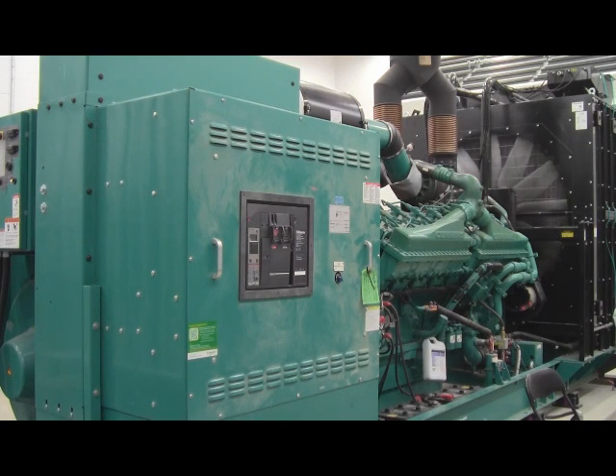This is the backup generator. It's all run to the PLC panel to kick in when the power goes out to the building and there's no power run into the ATS. It automatically transfers and the diesel generator kicks on. When it kicks on, the pumps don't even miss a beat. So if the power's off for 5 hours, it will run for 5 hours. It will keep running until the power is active back to the building.